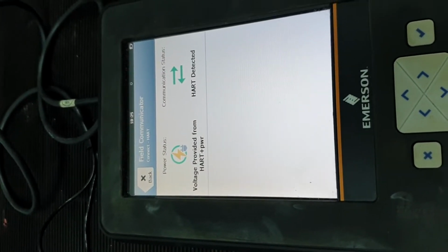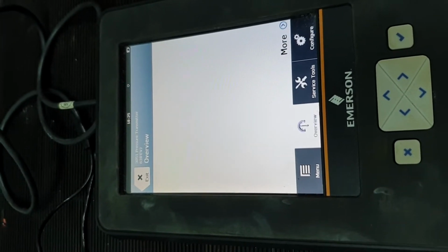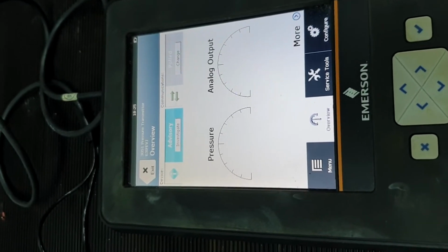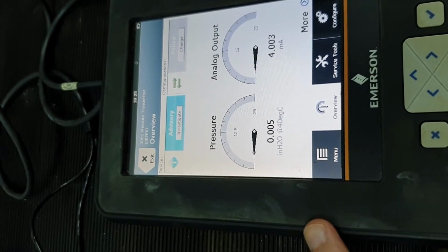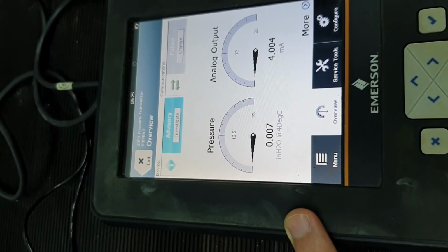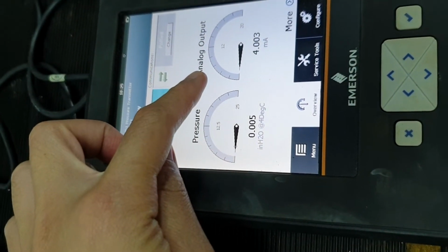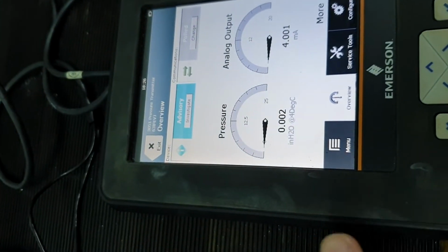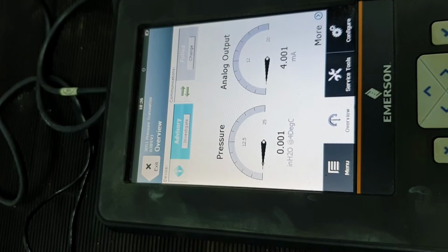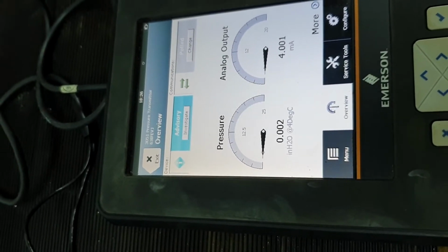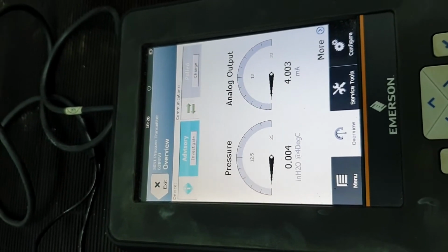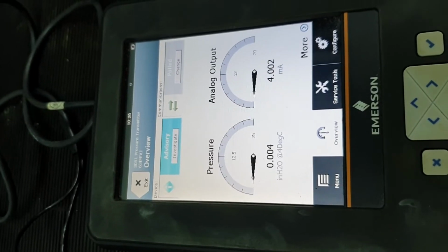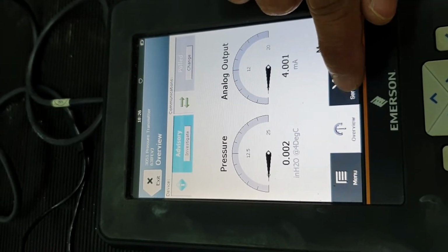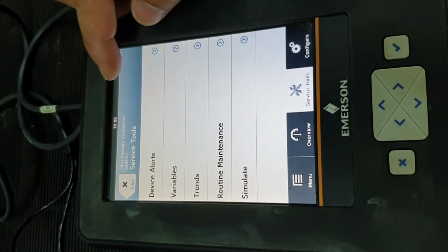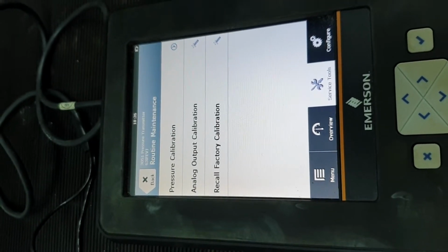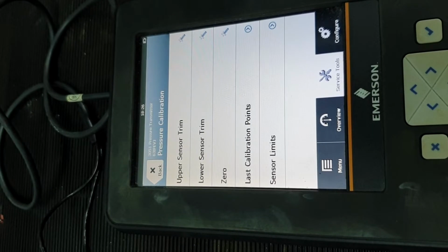Wait for a moment. Then you can see that there's a reading on the screen whereby we are using inches H2O as the pressure input, and the analog output is what we're going to measure. Looking at this screen, the pressure is out of scale, so we need to ensure that the readings are accurate. We will perform some fixing here by pressing service tool, routine maintenance, pressure calibration, and then we select 0.